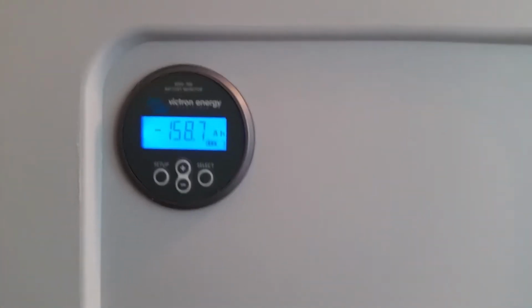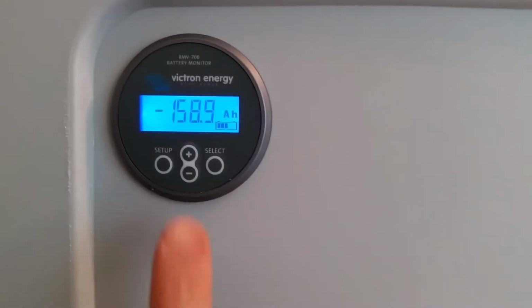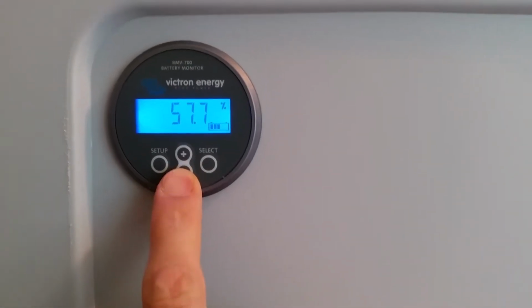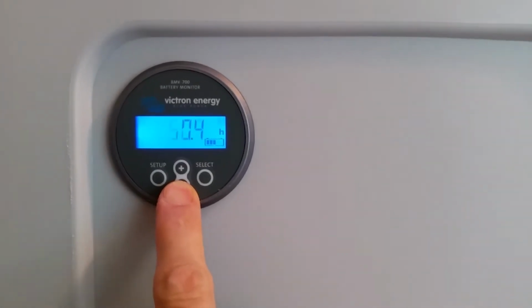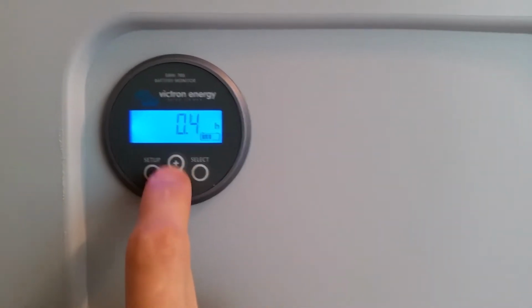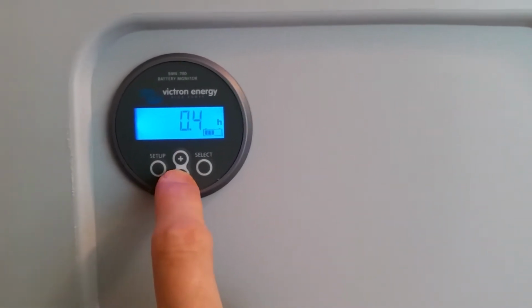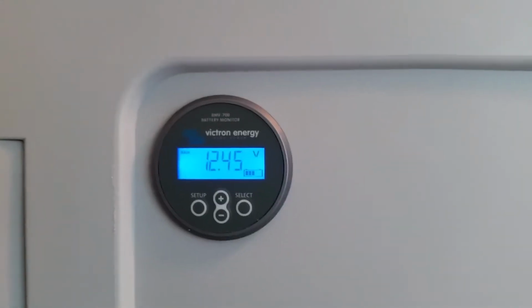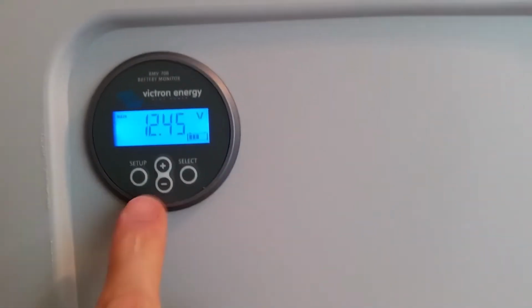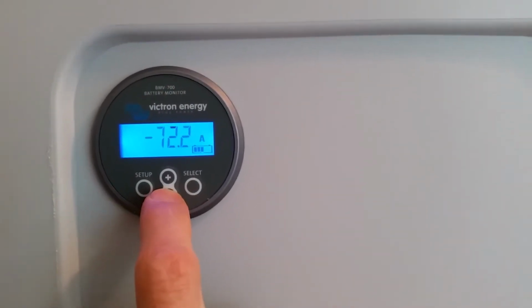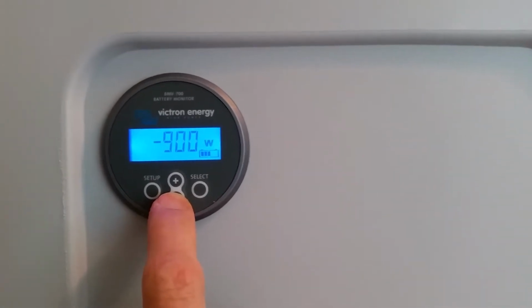Okay folks, we're a little over 2 hours into the test here, down to 158, 159 amp hours out of a 400 amp hour rated battery, so that's 57%. I don't know why it only shows 0.4 hours left, that doesn't make sense. Anyway, down to 12.45 volts, still pulling about 70 amps, 900 watts.